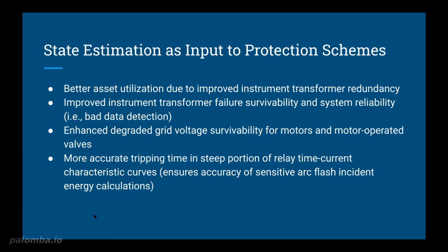Here we have state estimation as input to protection schemes. So in other words, what we're describing here is the use of state estimations as input to existing relay protective devices with their typical trip setting schemes rather than direct CT or PT measurements.